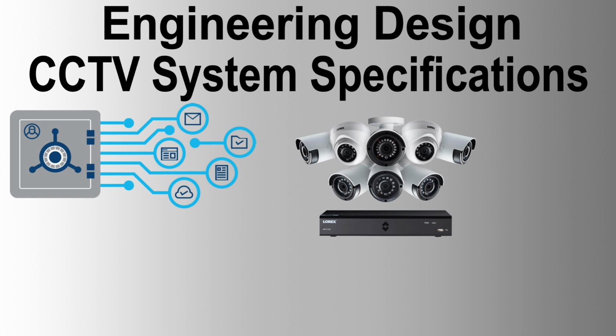All video transmission from cameras to their associated CCTV cabinets shall be via fiber optic cable. Each camera shall use dedicated fiber between the fiber optic transmitter unit located adjacent to or at grade level from the camera and the FO receiver located in the CCTV cabinet in the control room. The camera video transmission equipment shall be equipped for the return path from the CCTV cabinet to the cameras for the control of pan, tilt, and zoom functions. This shall be through separate fiber from the camera to the CCTV cabinet in the control room.